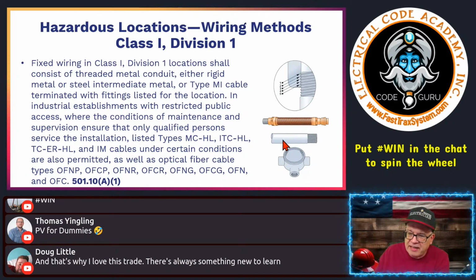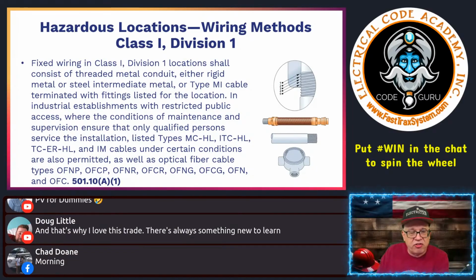ITC instrumentation tray cable, again, it's going to have the HL classification. TCERHL, that is not your normal tray cable. Even though it is exposed run, or extended run, however your flavor, that is very specific and it has to have additional testing on it. It's not just your normal tray cable.